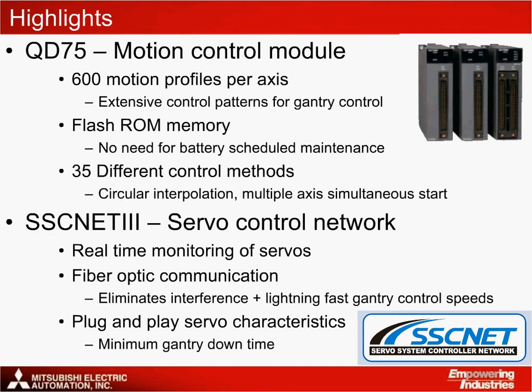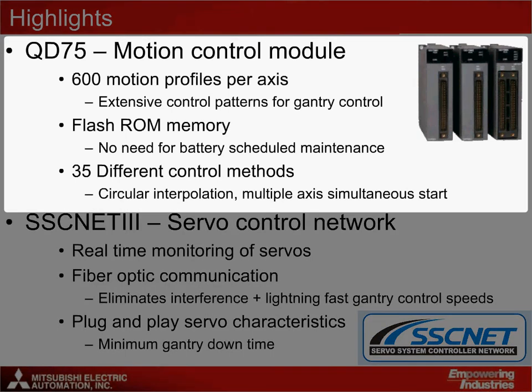At the centre of the application is the QD75 motion control module, which is an ideal addition to the Q-series PLC for one, two or four axis control. The QD75 can store 600 motion profiles per axis, giving it a large capacity for programs that rely on a high number of movements. A flash memory removes the need for scheduled maintenance checks and ensures no loss of data associated with battery-backed motion control modules. The QD75 has a variety of control methods such as circular interpolation and multi-axis start, that make setting up gantry control movements easy and allow safe transportation of materials.